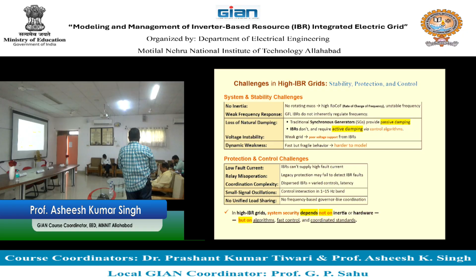Clear? Then protection and control challenges, low fault current. IBRs cannot supply high fault current due to limitation of the current capability of the components. Clear? Then comes relay misoperation, means legacy protection techniques, which are mostly for AC grids, may fail to detect IBR faults. Coordination complexity, IBRs are dispersed, means distributed generation.